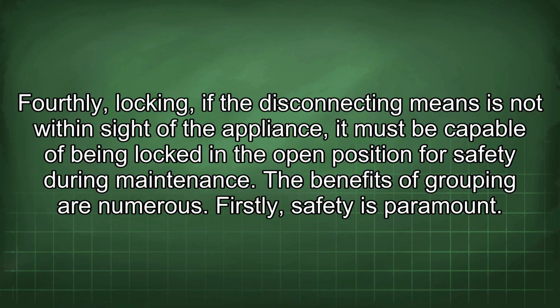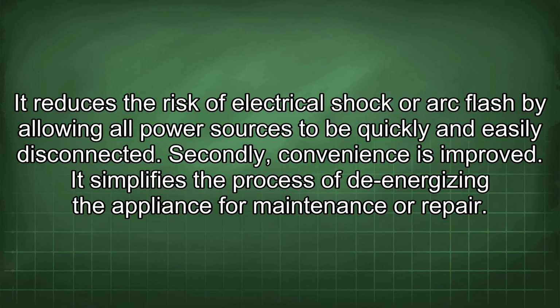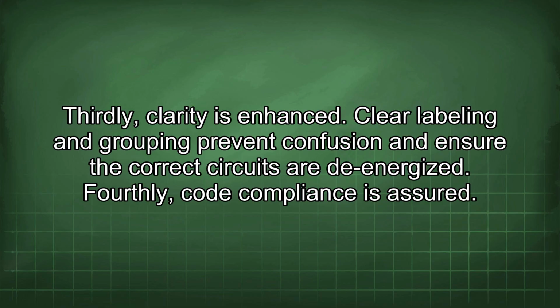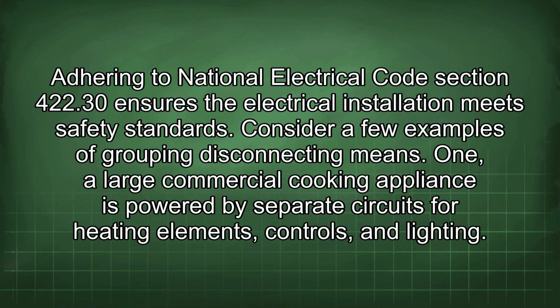The benefits of grouping are numerous. Firstly, safety is paramount. It reduces the risk of electrical shock or arc flash by allowing all power sources to be quickly and easily disconnected. Secondly, convenience is improved. It simplifies the process of de-energizing the appliance for maintenance or repair. Thirdly, clarity is enhanced. Clear labeling and grouping prevent confusion and ensure the correct circuits are de-energized. Fourthly, code compliance is assured. Adhering to National Electrical Code Section 422.30 ensures the electrical installation meets safety standards.